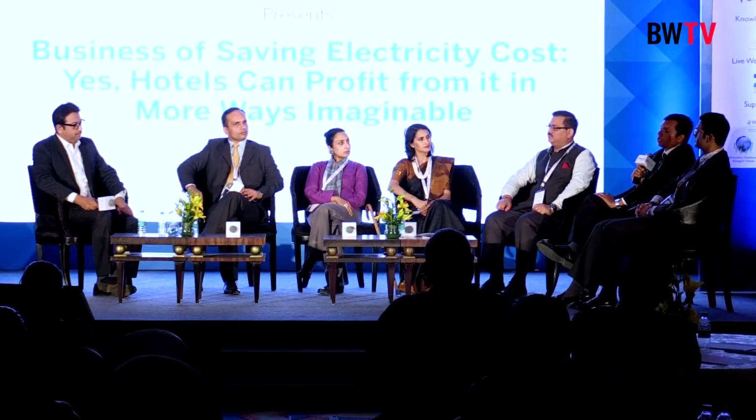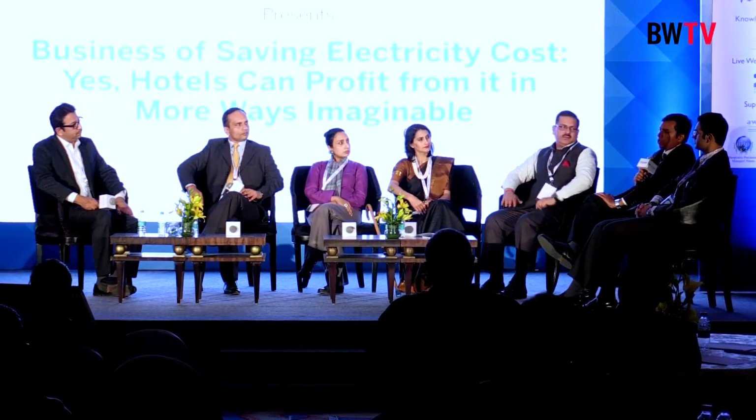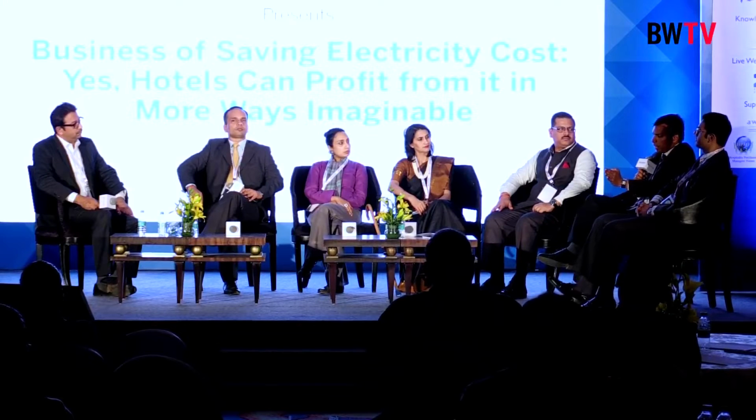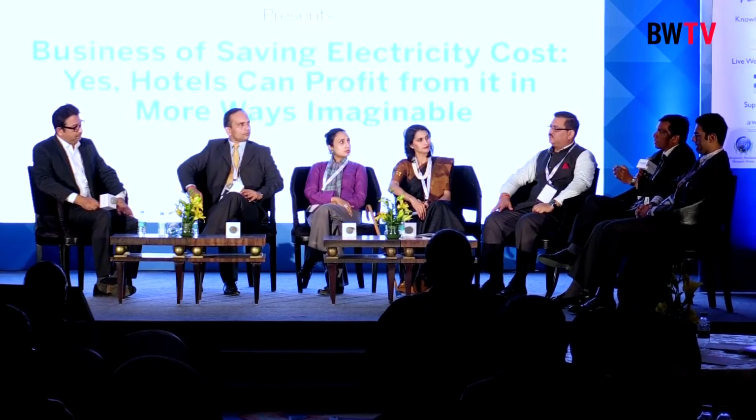If we go with the short-term open access, it's coming around 6.7527 rupees. So what we feel is that 1 rupee for a hotel, like our demand is something around, MD goes up to 1500 kVA. So we are expecting from starting we can do 0.5 megawatt, and then slowly we'll increase to 1 megawatt. And we have calculated something around 3 lakhs, which is roughly approx 6 to 7% reduction in the HLP cost.